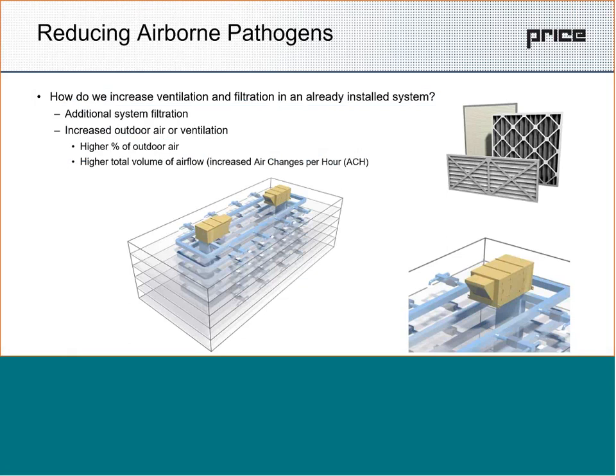So there are a couple of issues with trying to do this in retrofit buildings. Chris kind of mentioned it. A lot of the times, if you want to increase filtration in a space with your traditional system, we're finding that a lot of the air handlers can't handle the increased filtration. There are cases where you can just slide it in and maybe adjust some pulleys or turn up the VFD, but that's not always the case.